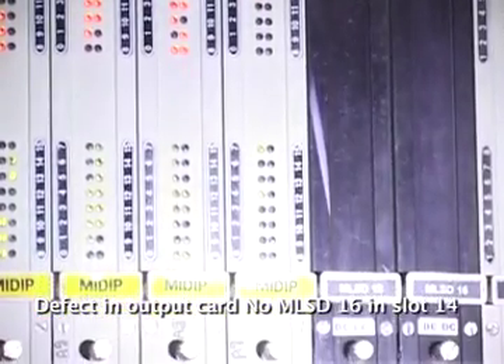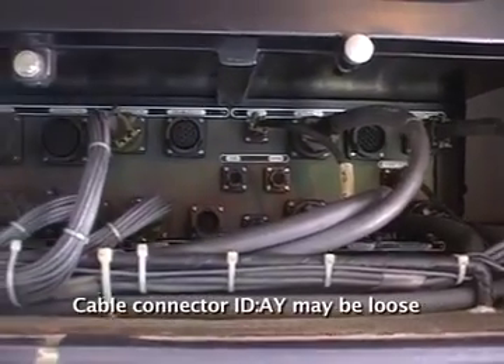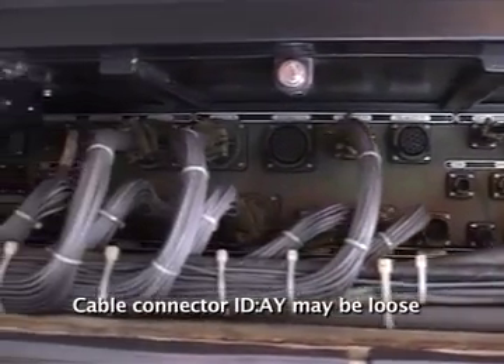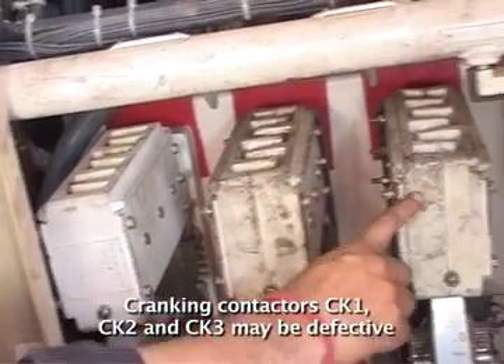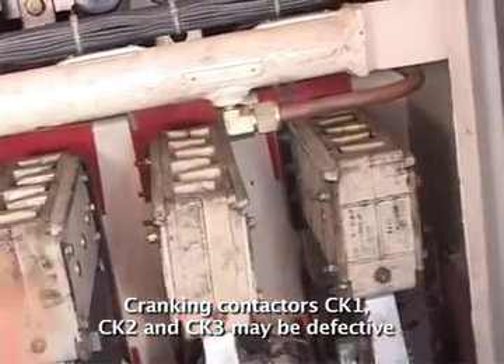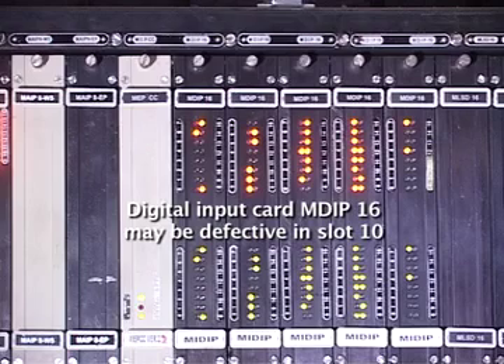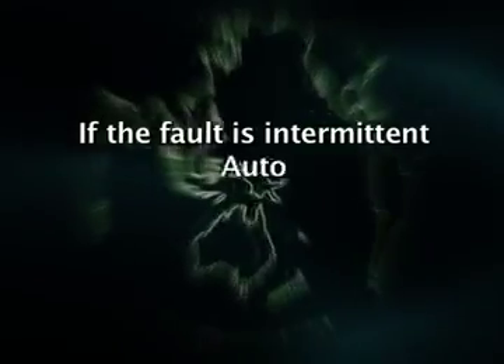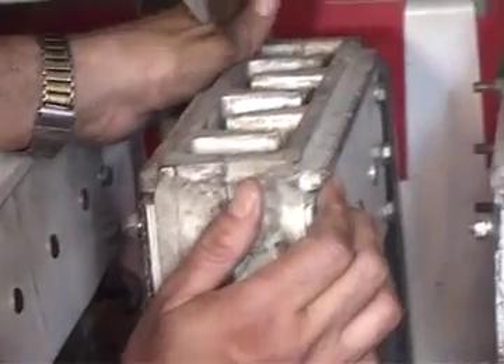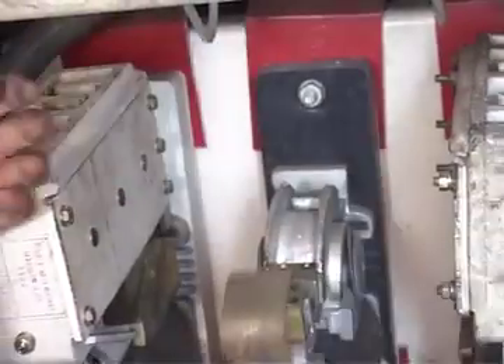MLSD16 in slot number 14, cable connector ID AY may be loose, cranking contactors CK1, CK2 and CK3 may be defective, digital input card MDIP16 may be defective in slot 10. Action by driver. This message comes only at the time of engine cranking. Be sure. If the fault is intermittent, automatic recovery on opening of auxiliary contact of CK1, CK2 or CK3.